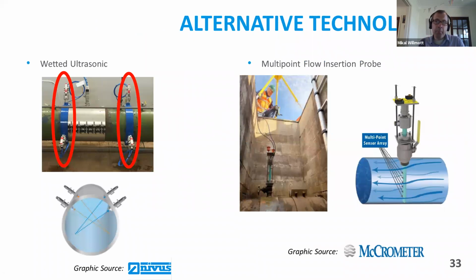There are a couple of alternative technologies that are worth mentioning, and we've installed both of these in Severn Trent fairly recently. So one is wetted ultrasonics, and you see that on the left-hand side, where you put transducers that go slightly into the main. That means that they don't have to worry about pipe wall thickness, which can sometimes also cause errors, and they actually see what's happening in the main. So again, we've installed a couple of them in Severn Trent, and again, lots of testing's been done on them, and that's something that I would recommend as a good product to consider using.